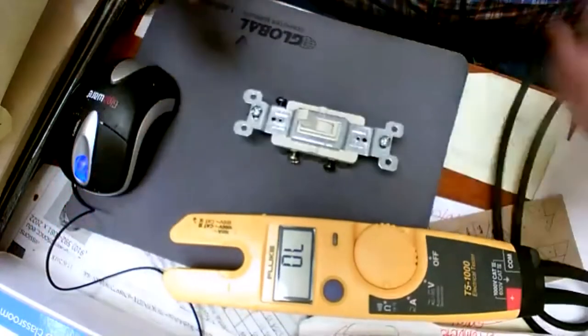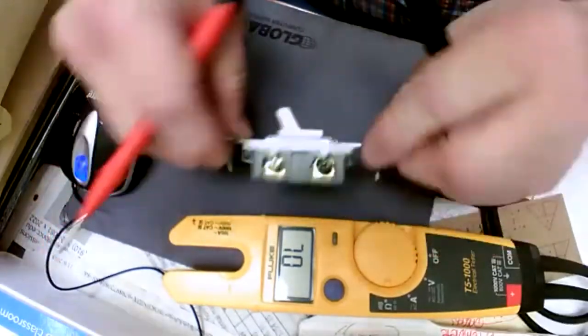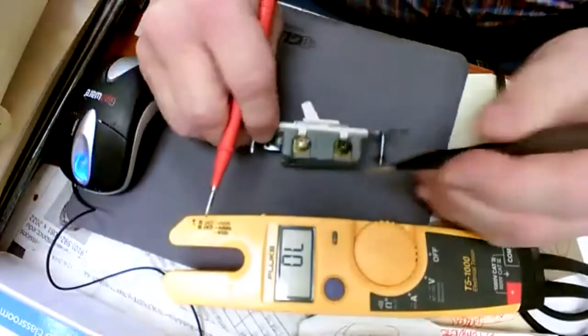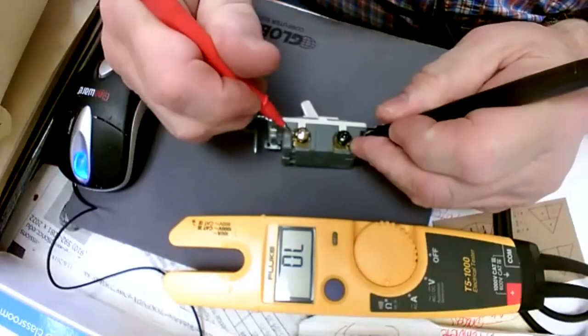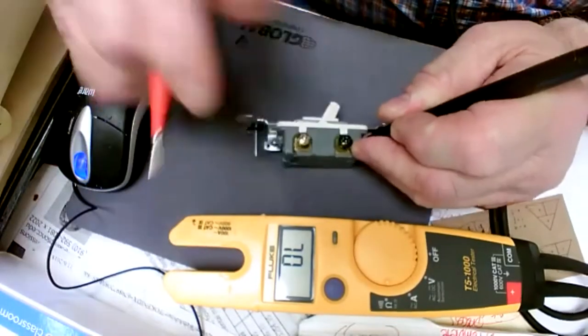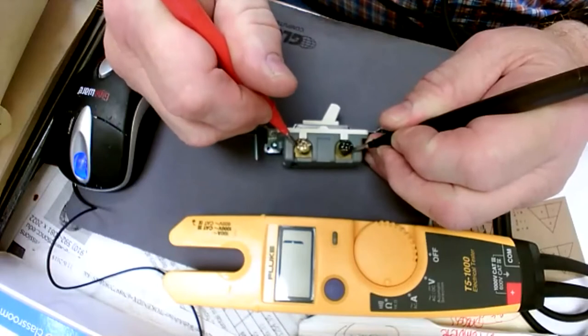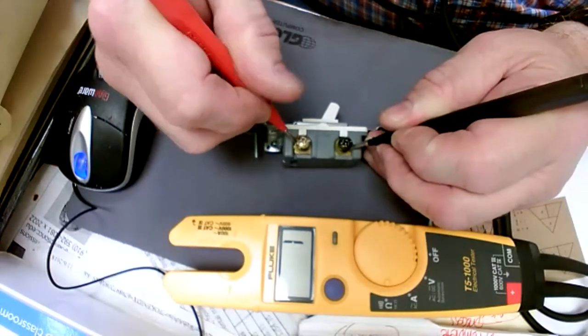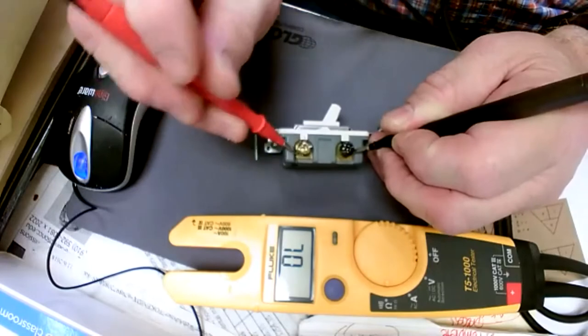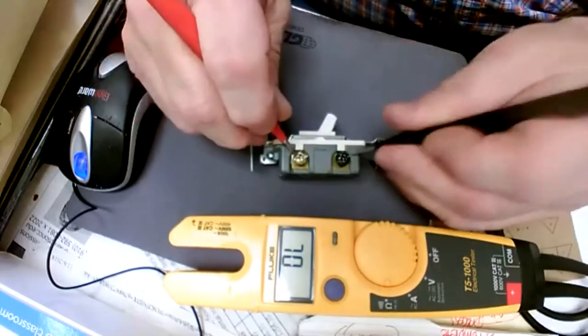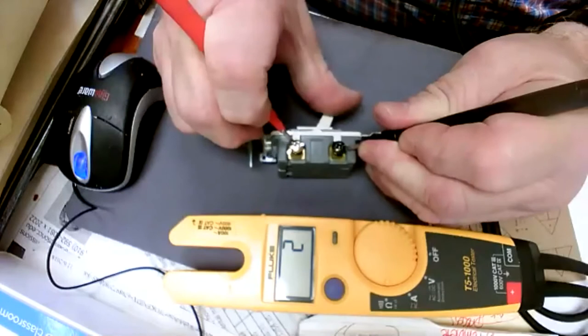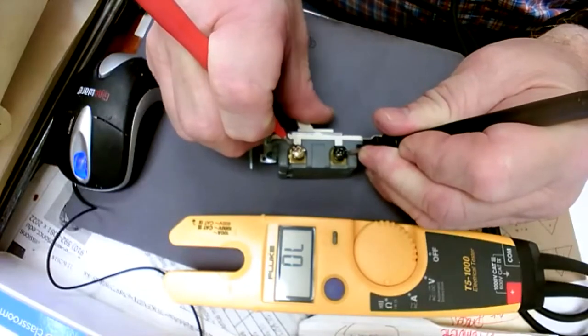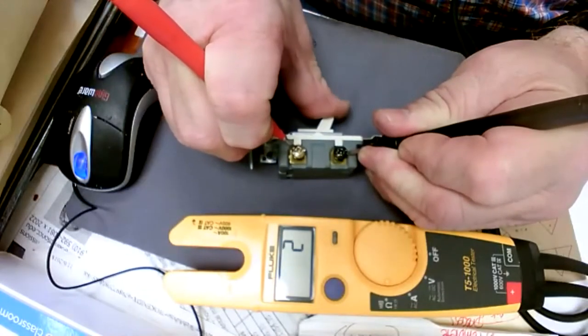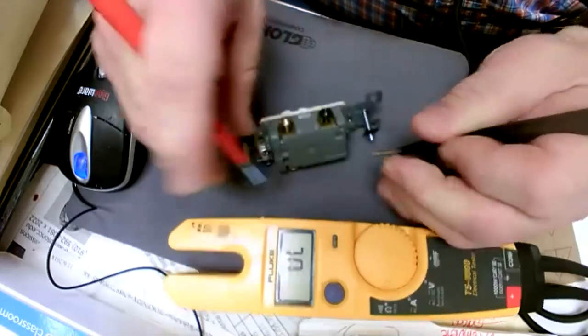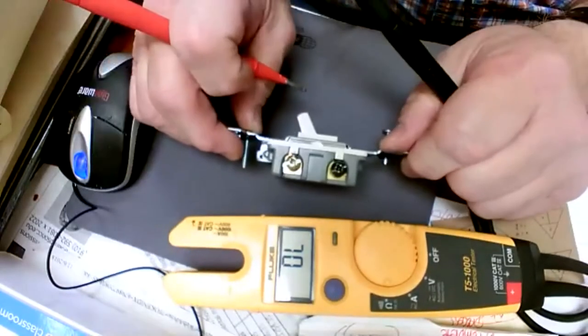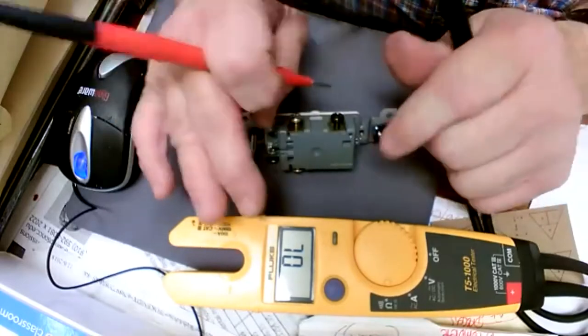Now, if I just do a continuity check on part of the switch here, and I go from here to here, I don't have a connection. But when I flip the switch, then you see I have a reading right there of 1 ohm. And then when I cut the switch off, I have an OL. Now you can test a switch with an ohm meter when it's out of the circuit, when it's not hooked up to power, and that's fine.